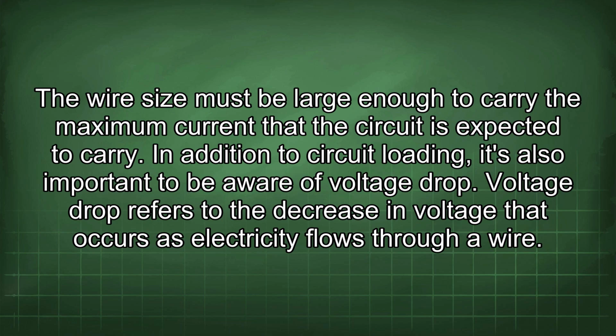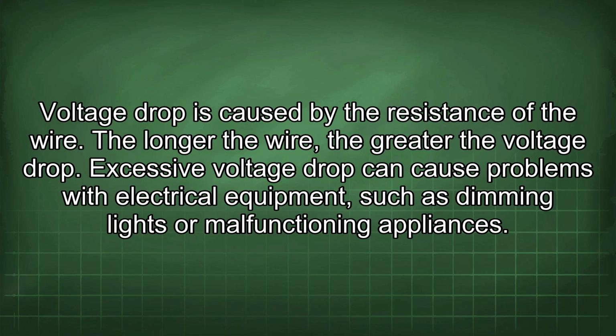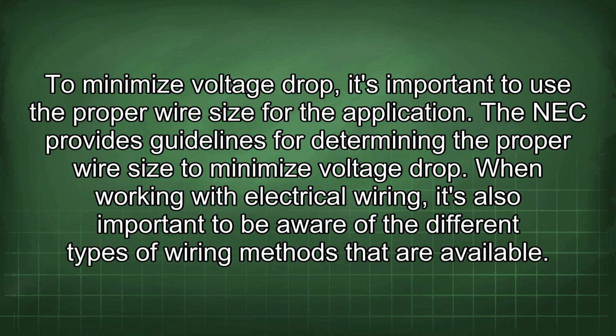In addition to circuit loading, it's also important to be aware of voltage drop. Voltage drop refers to the decrease in voltage that occurs as electricity flows through a wire. Voltage drop is caused by the resistance of the wire. The longer the wire, the greater the voltage drop. Excessive voltage drop can cause problems with electrical equipment, such as dimming lights or malfunctioning appliances. To minimize voltage drop, it's important to use the proper wire size for the application. The NEC provides guidelines for determining the proper wire size to minimize voltage drop.